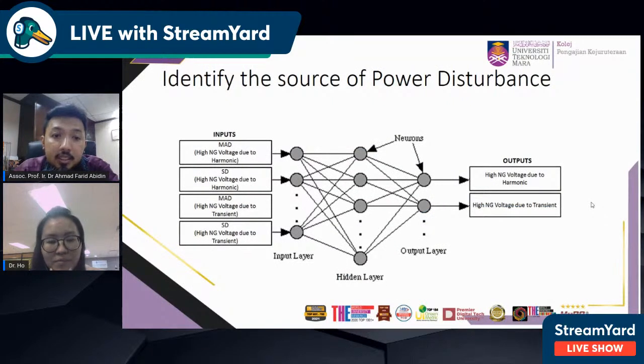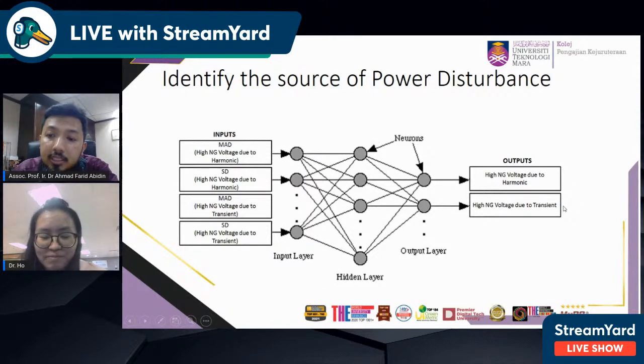Okay, this is how the simple neural network works to identify the disturbance which is related to the high neutral to ground voltage or high neutral to earth voltage. We put in two outputs, which are neutral to ground voltage due to the harmonics and neutral to ground voltage due to transient. Okay, if due to transient, we can go into detail, where transient can be classified or related to two issues, which are loose connection as well as lightning.